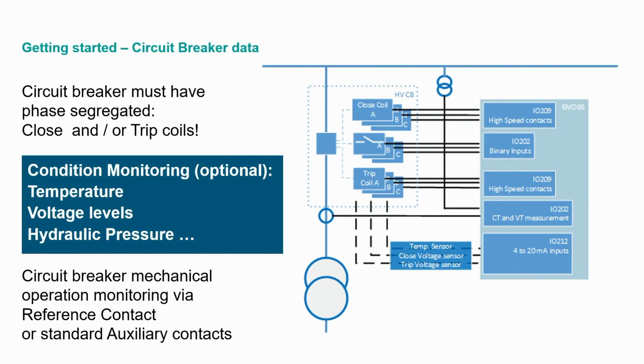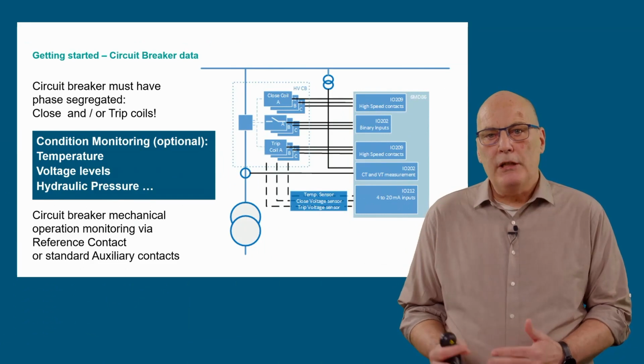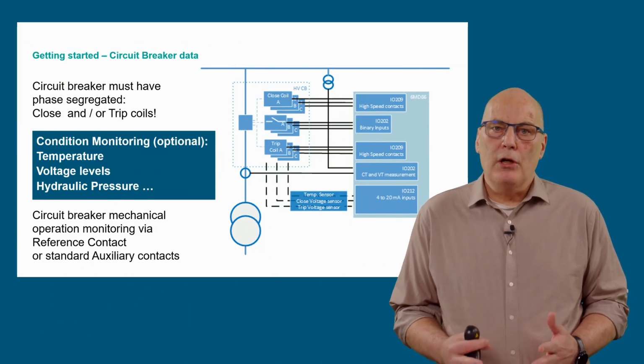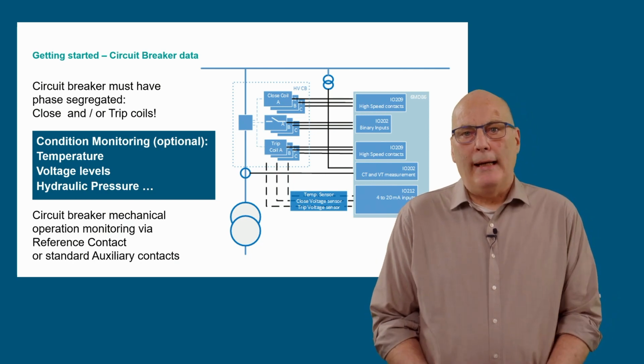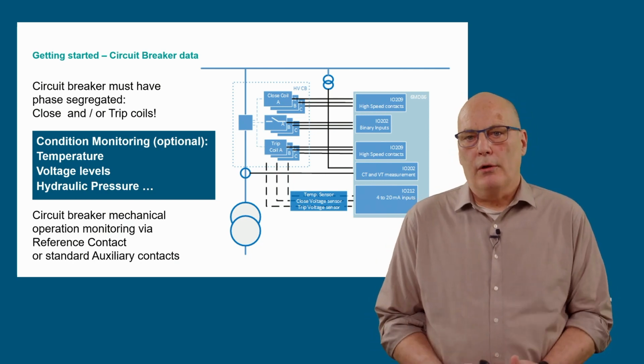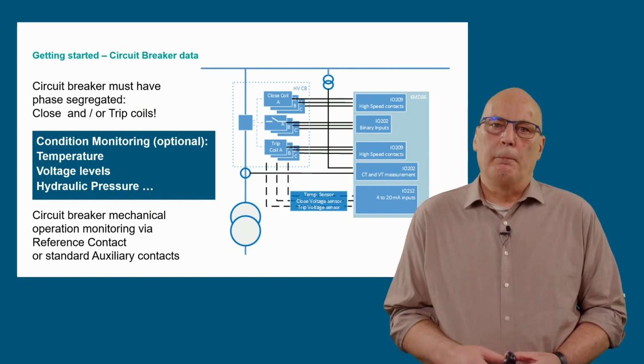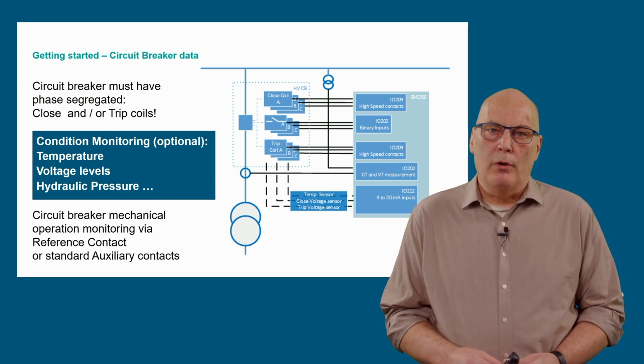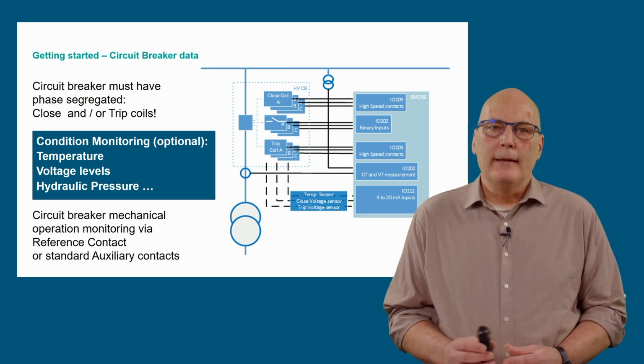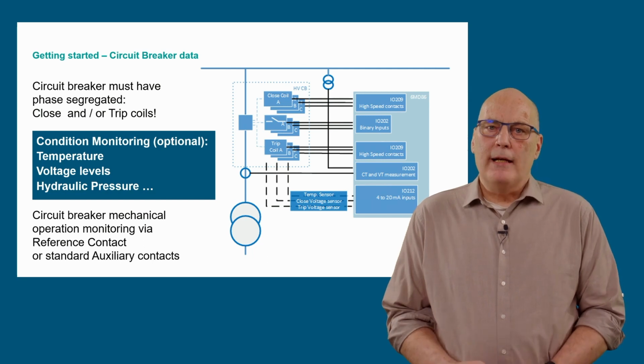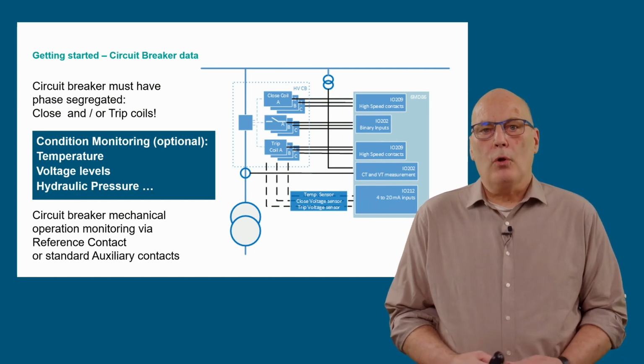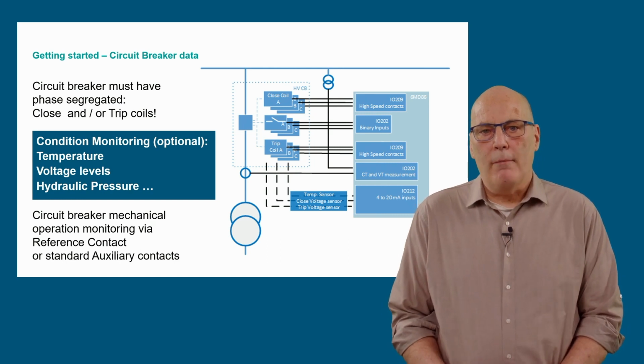The circuit breaker is a very important central component of the point-on-wave application. For the intended application, for example point-on-wave closing, the circuit breaker must have phase-selective closing coils to enable each phase to be closed independently. This is shown in the diagram where for each pole, A, B and C, there is a separate closing contact in the IO209 at the top, as well as a separate trip contact for each pole in the IO209 in the middle. This phase selective connection of the closing and or trip contacts is a must for the point-on-wave application.